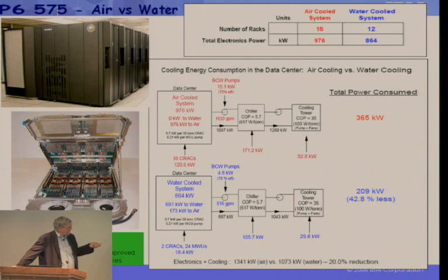Total electronic power on the air is 976 kW. On the water, it's 864. So there's a big difference right there. If you look at the air-cooled system, all the infrastructure to support the air cooling, chillers, cooling towers, CRAC units, all that, it's 365 kW to support that 976. For water cooling, it's 209 to support the 864. Just on the cooling energy, it's about 40% reduction in the data center. And on the total energy, if you include electronics and cooling, it's about 20% reduction. So big improvement on energy savings, looking at the whole problem.